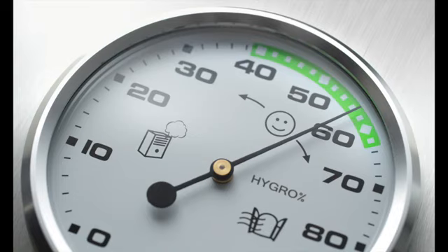Resistive steam humidifiers are often the close controlled humidifier of choice, but ultrasonics might sometimes be used for very small areas. There's also a type of induct humidifier, a hybrid system that offers close control by combining evaporative and spray systems. Now, all of these can control to around plus or minus 1 to 2% relative humidity. Beyond that, if a project needs plus or minus 5% control, then electrode boiler steam or spray systems become an option. Then for an even wider plus or minus 10% RH, we can consider evaporative or gas-fired steam units.